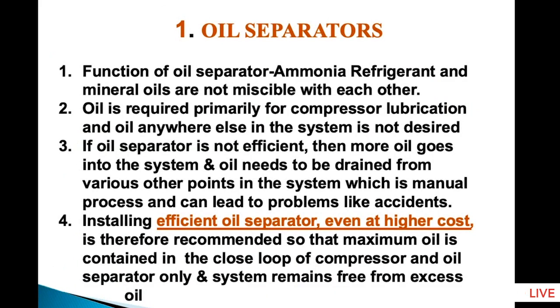Next, we will go to individual pressure vessels. We have seen now how to calculate the design thickness of the pressure vessels, how to use correct welding rods, how to use correct material. Now we go to the individual vessels. The first vessel is the oil separator, which is used for separating ammonia and oil, because ammonia and mineral oils are not miscible with each other, unlike your CFC, HFC gases, where the oil is mixed and carried in the system. In ammonia plants, oil is immiscible.